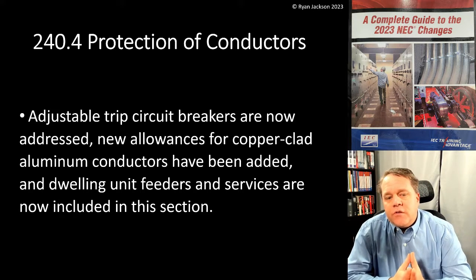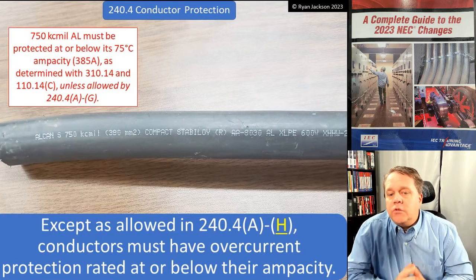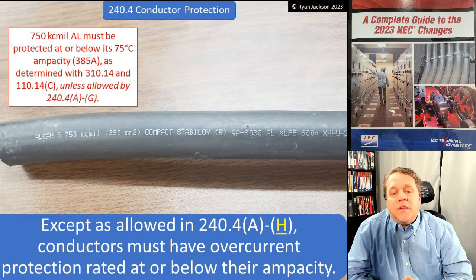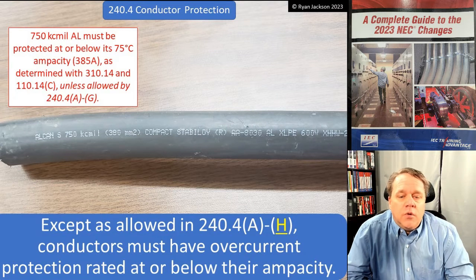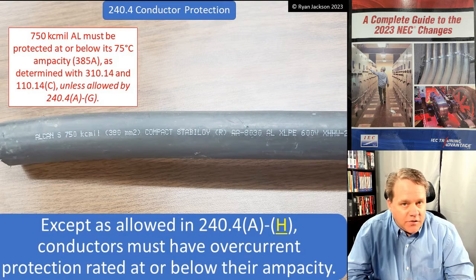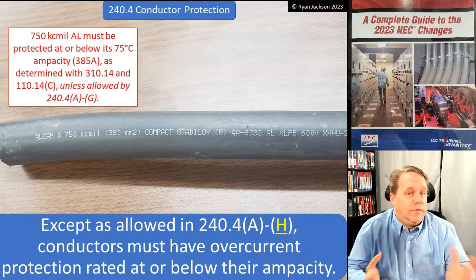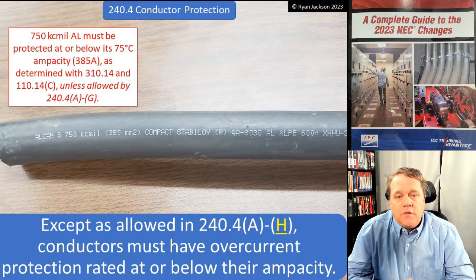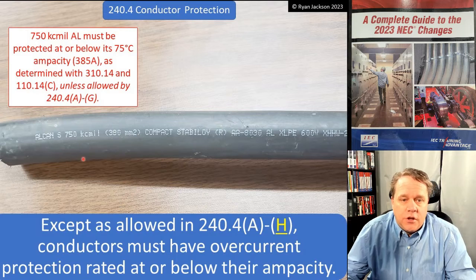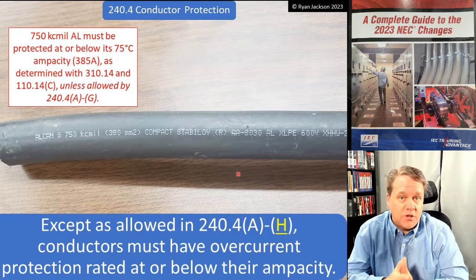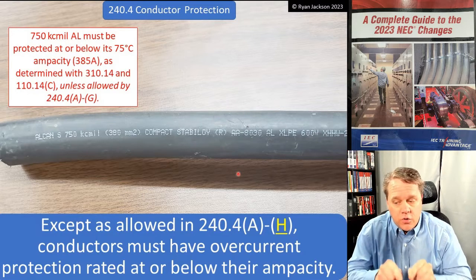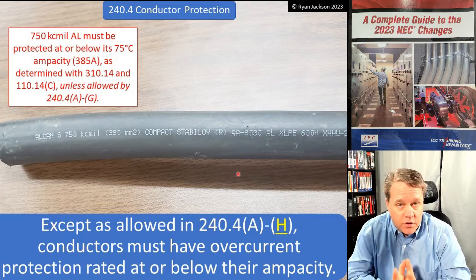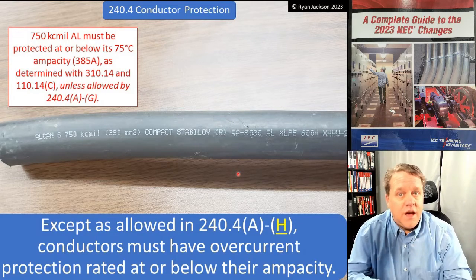240.4 starts with a general requirement: except as allowed in (A) through (H), conductors must have overcurrent protection rated at or below their ampacity. The ampacity of a conductor is the amount of current it can carry continuously without exceeding its temperature rating. For example, 750 kcmil aluminum at the 75-degree column — we use 75 degrees because of 110.14(C) for termination ratings — has an ampacity of 385 amps.